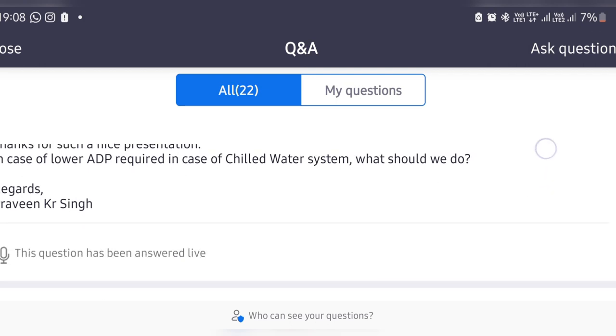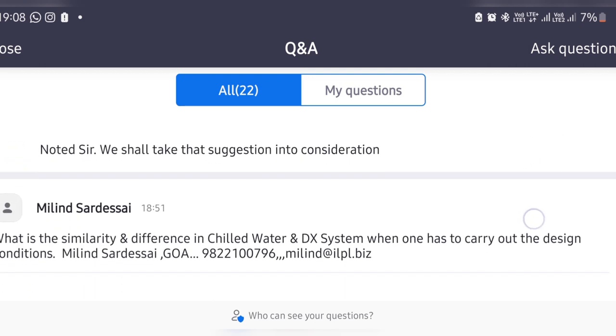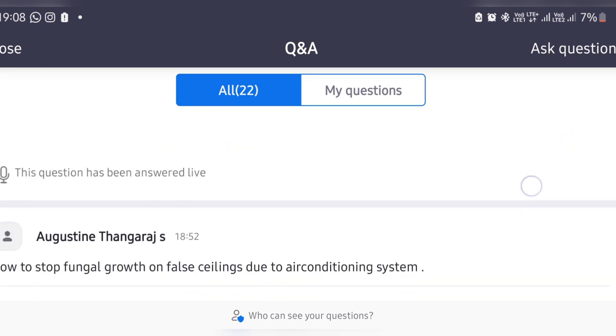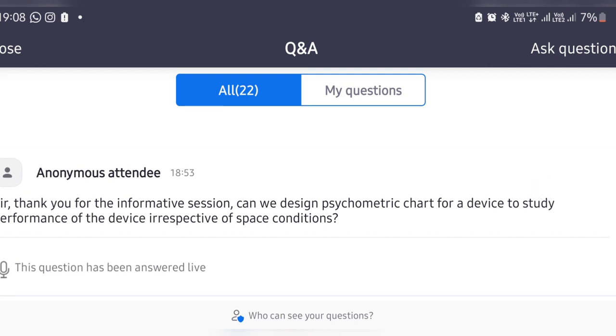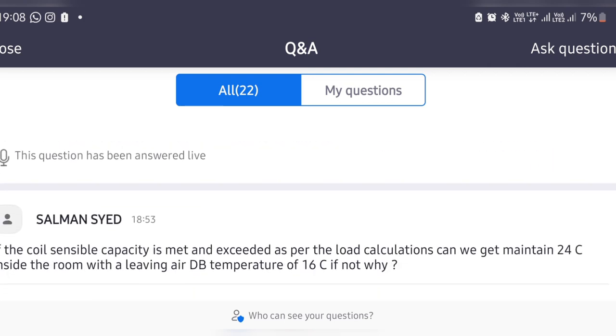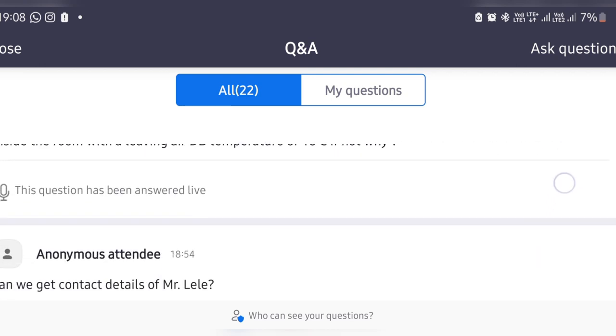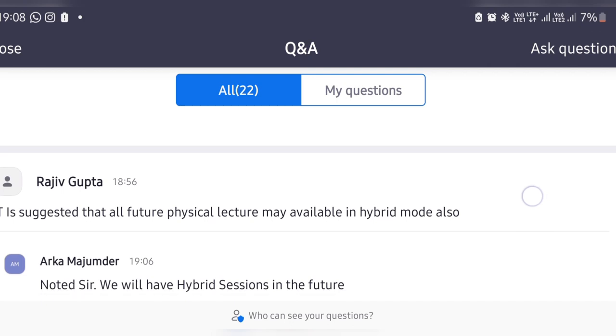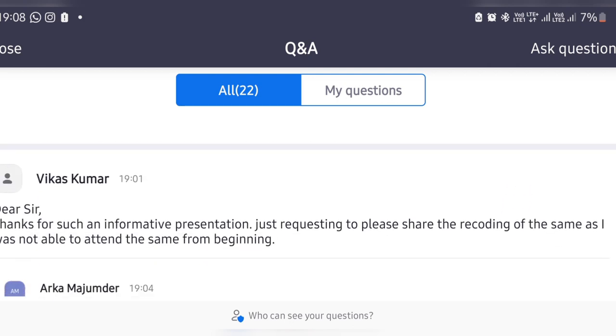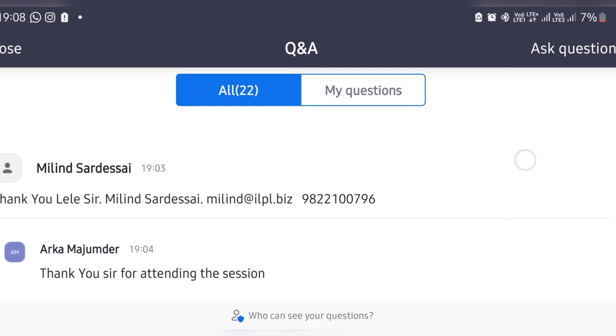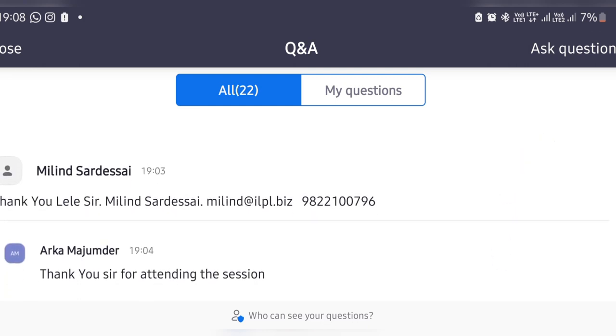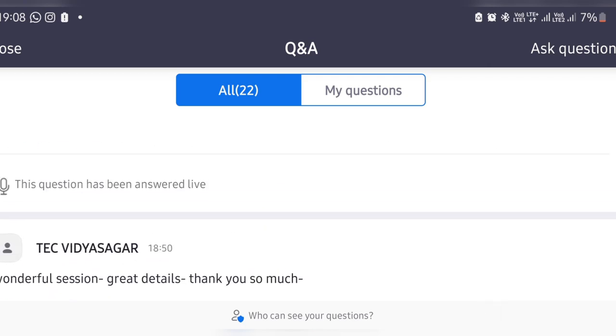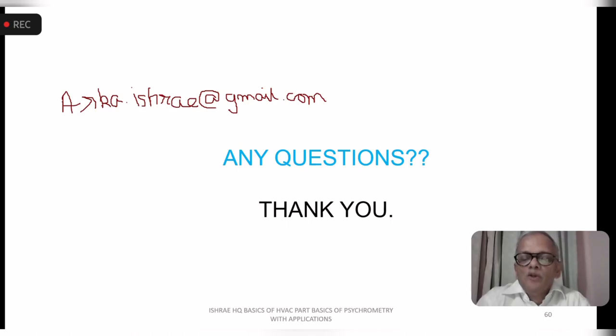Generally, what is done is we calculate the amount of air to be circulated or calculate the total heat, and then you always have this proportion of sensible and total. Now your equipment has to be selected carefully. We have to make sure that we have enough sensible as well as enough latent capacity. There are cases where sensible can be met, but latent cannot be met in case of higher latent loads. In that case, you will have to go to the next equipment size, which has the latent capacity, because that's what was the statement in the Carrier system design note for equipment selection. The plant has to be selected to meet both sensible as well as latent capacity.